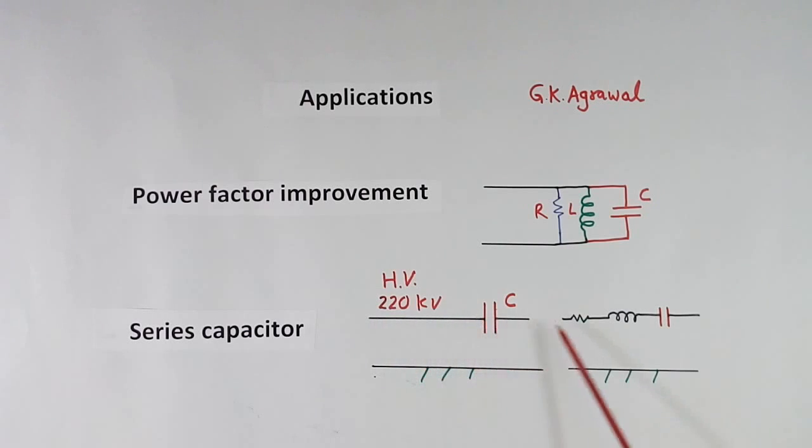Now this wire will have resistance and inductance. This resistance and inductance is the value of R and L of this wire, is not connected extra. Because of this L, transmission capacity of this transmission line comes down. To improve that, we connect a capacitor in series. This capacitor will cancel out this inductance, and power transmission capacity of this transmission line will improve.